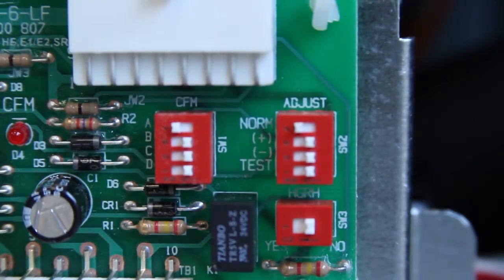The control will send a 24-volt signal to the board during a call for dehumidification, and while the unit is operating and cooling, it will reduce the CFM of the motor by up to 30%. The other option is hot gas reheat, which is not installed on this unit, and you should consult the installation and maintenance manual for the proper setup for that mode of operation.